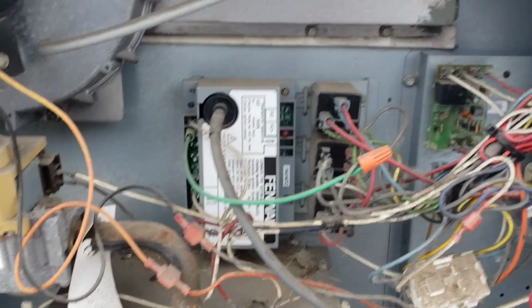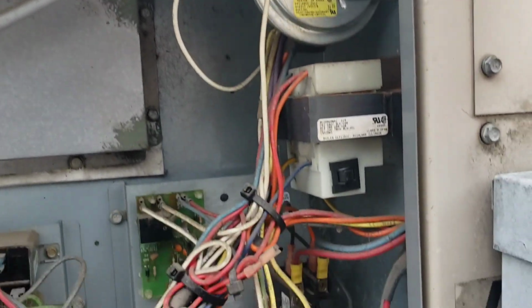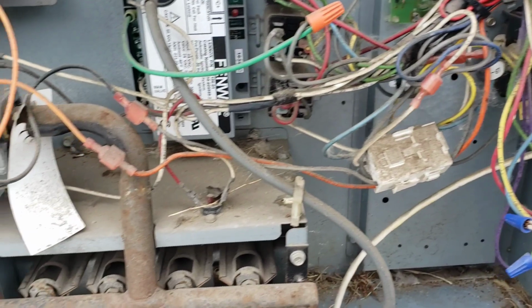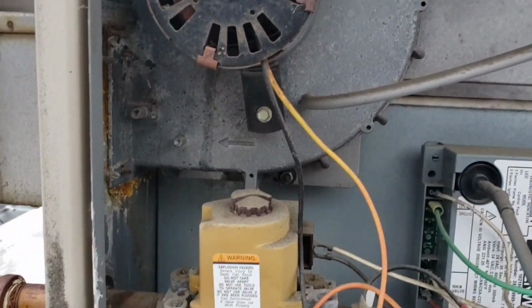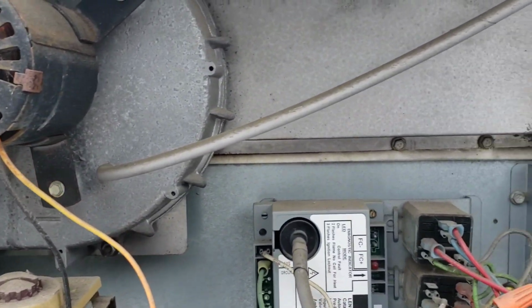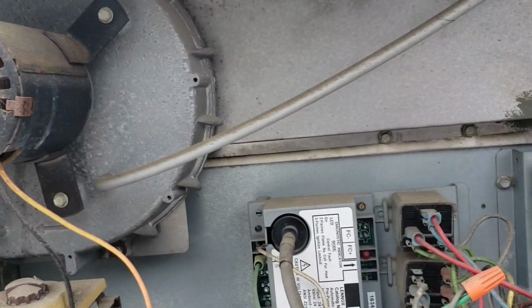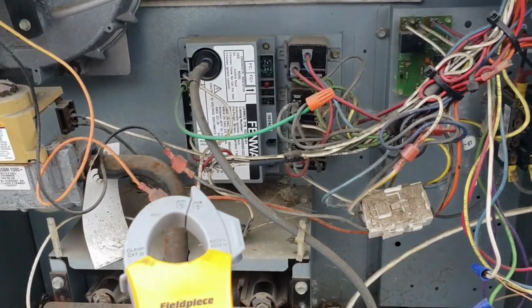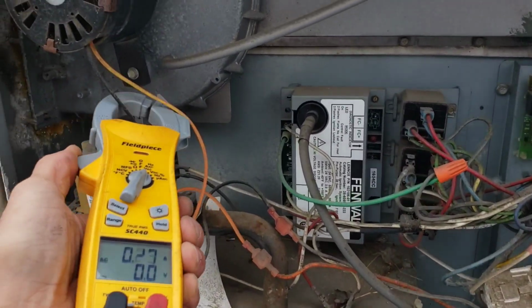It's a good question. Let's let it run for a little while, see what happens. Maybe after it runs and runs and runs all day, the inducer goes bad - it's gonna amp draw our inducer. Or the inducer seizes up once that bearing gets hot.